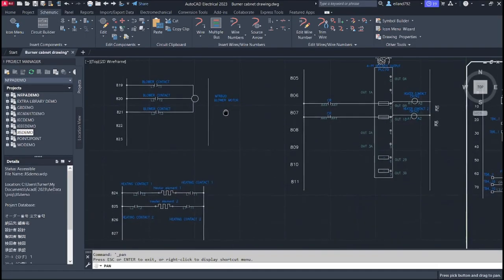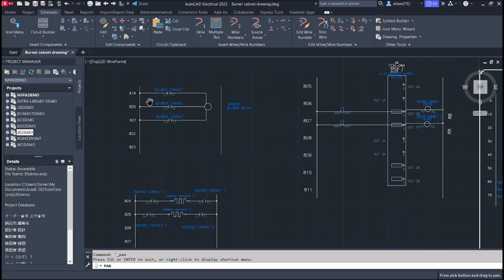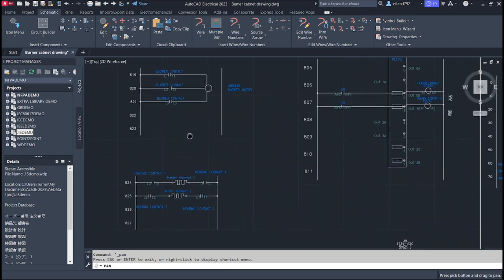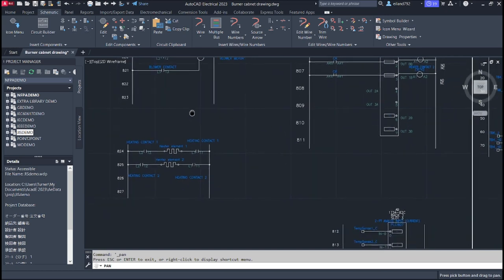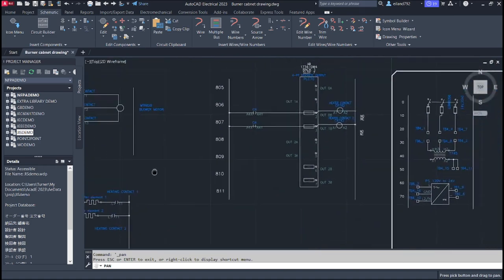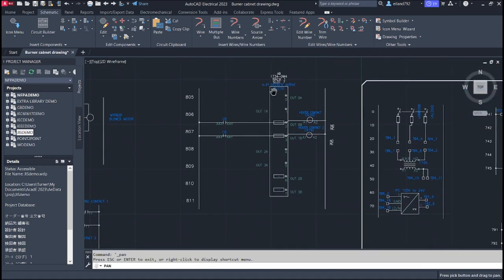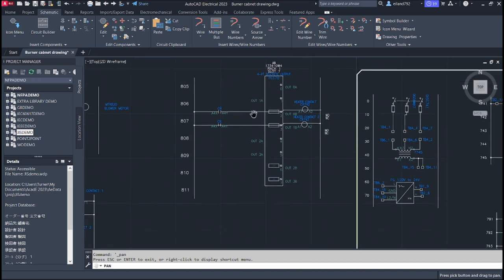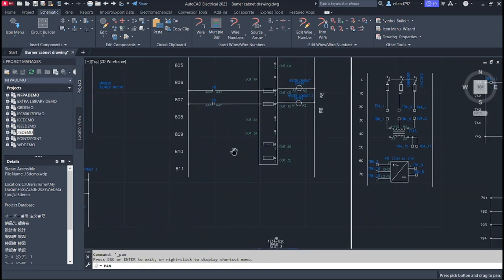All right, so here we have my CAD drawing. Right here we have our blower motor and the contacts that are used to start it. Same with the heating element. We have 2 phases going into the heating element. Our output card for our I/O. These outputs power the power on the heater contacts.